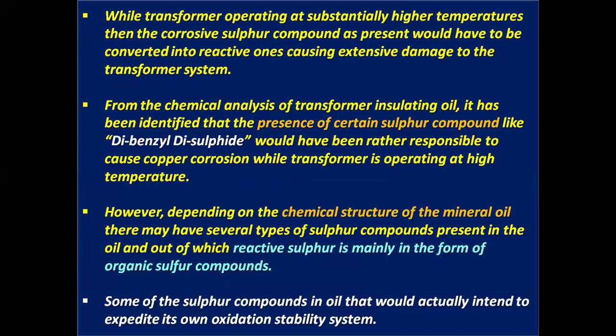While the transformer is operating at substantially higher temperatures, the corrosive sulfur compounds present would be converted into reactive ones, causing extensive damage to the transformer and its insulation system. From the chemical analysis of transformer insulating oil, it has been identified that certain sulfur compounds like dibenzyl disulfide would be responsible for causing copper corrosion while the transformer is operating at high temperature.